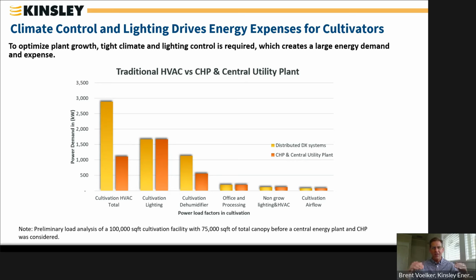What you want to do is level your load as much as possible, by alternating flowering rooms and staggering veg rooms, maintaining as level a load as you can for both utility power and CHP. The lower your demand and the more even it is, the better you can size your CHP to run at a nice base load, full load all the time, getting maximum value out of the engine. Similarly with utility power, the lower and more level it is, the less copper and other equipment they need to deliver that power. So the principles are the same either way.